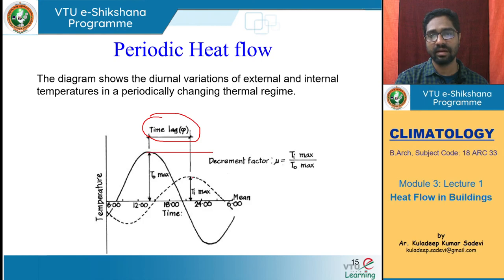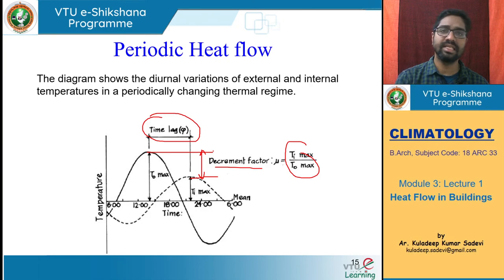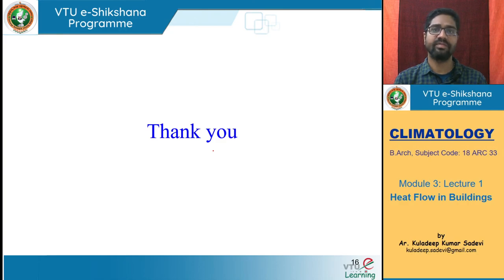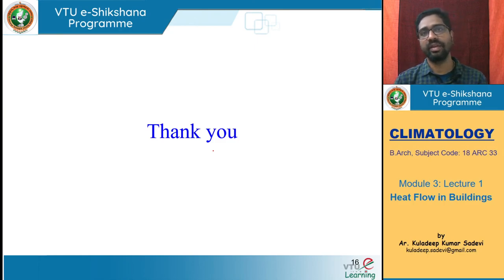The time gap between outdoor maximum temperature and indoor maximum temperature is called time lag. The ratio of maximum indoor temperature difference to maximum outdoor temperature difference is called the decrement factor. We will discuss these terms and more introductory concepts about heat gain and heat flow into buildings in the next lecture. Thanks for being with me — we will see you in the next one. Thank you.